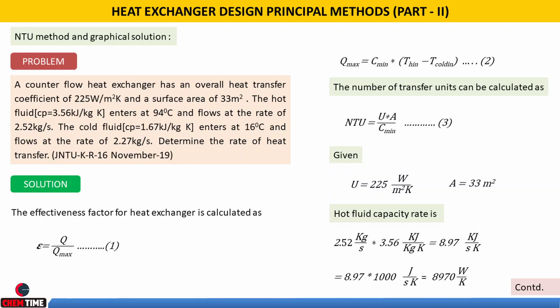First, we write the formula for the effectiveness factor ε = Q / Q_max. As discussed, Q_max = C_min × (T_H,in − T_C,in), where C_min is the minimum of the capacity rates of the hot and cold fluids. We need to use a graph that plots NTU for different values of C_min/C_max, which gives the effectiveness factor.